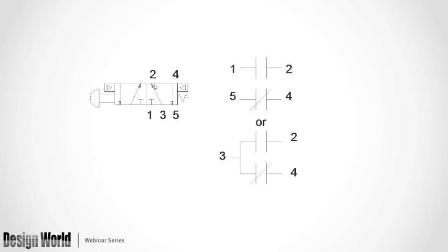Now, typically these valves are very small in size. I've seen them 3/4 of an inch square and only maybe 2 inches long. One of the unique things about these little valves is the long-term life. Many of these little valves, what they will do is they'll bring an airline into port 3 and come out of 2 and bring a sensing line over to push on this pilot over here, which automatically shifts the valve, directing air from 3 to 4, and then they hook a sensing line up to here to push it back. And it puts this valve into oscillation, a very, very high speed oscillation.